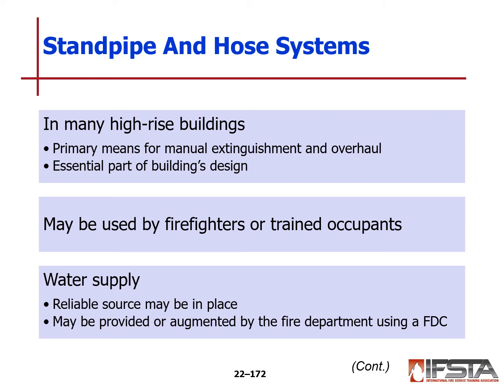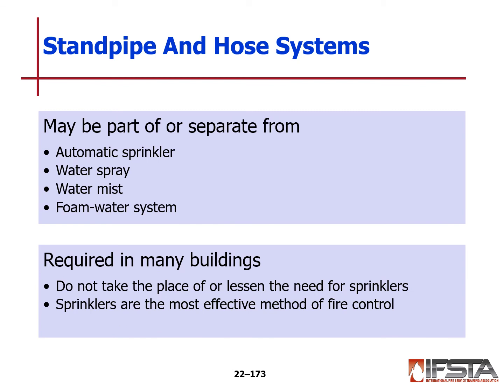Primarily a means for manual extinguishment, also used for overhaul, they are an essential part of the building's design. They may be used by firefighters or trained occupants. If they have hose systems and obtainable valves, they can be used by trained occupants as well. Water supplies: a reliable source may be in place, or may be provided or augmented by the fire department using the fire department connection. These systems may be a part of or separate from the sprinkler system itself, water spray systems, water mist, or foam systems. They are required in many buildings. They do not take the place of or lessen the need for the sprinklers. The sprinklers are the most effective method for control until the fire department arrives.